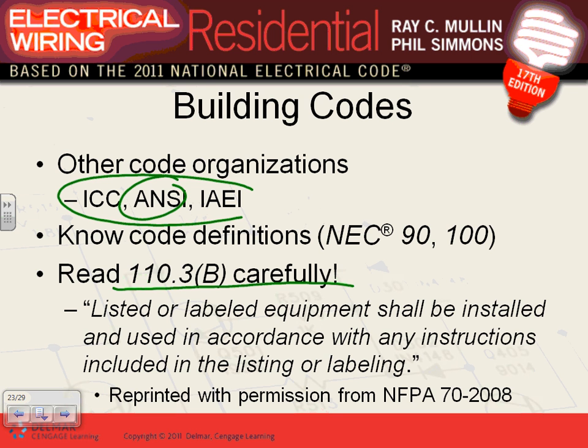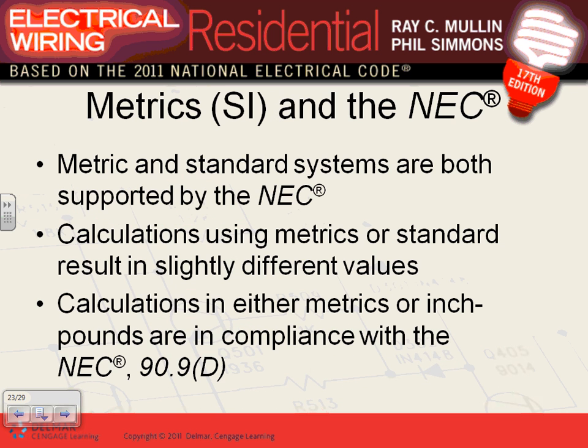For example, can I put this fixture outside in a parking lot? It's listed and labeled, but not for an outdoor wet location, so no. That's the whole point of listing and labeling - very important. As engineers, you'll face this all the time, especially with cheap equipment bought from other countries. You always have to check: is it listed and labeled, and is it installed according to that listing?